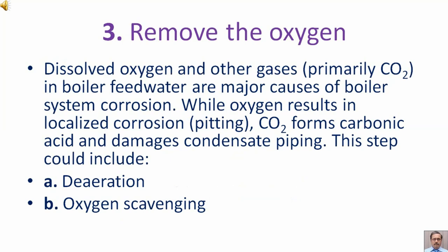Third step, remove the oxygen. Dissolved oxygen and other gases, in other gases, we include primarily carbon dioxide, in boiler feed water are major causes of boiler system corrosion.